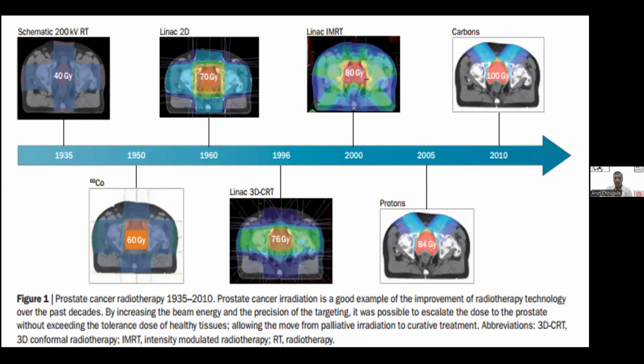With the linac, we could still increase to 70 gray. Then linac 3D CRT, conformal therapy with imaging and all those things. Computer treatment planning systems, 76 gray or 80 gray, linac IMRT 80 gray, 84 gray, 100 gray with carbon. This is the biological dose. The physical dose will be hardly 20 to 30 gray. So you can see with these advanced technologies, we are able to increase the dose to the tumor.